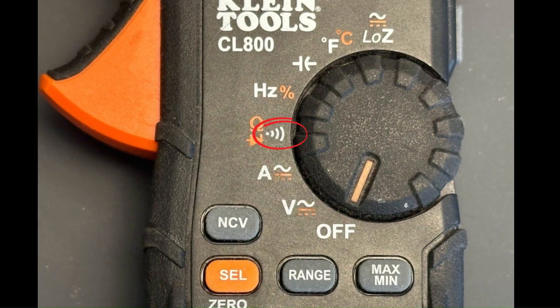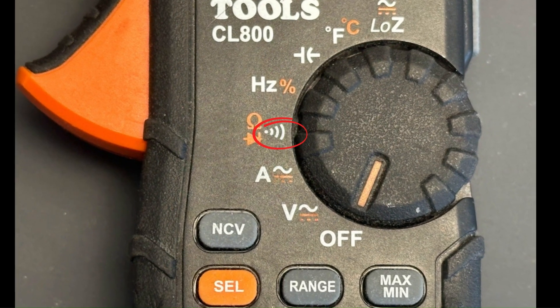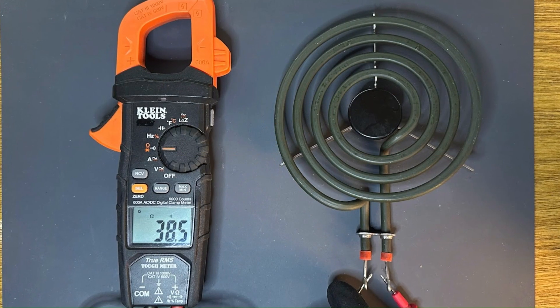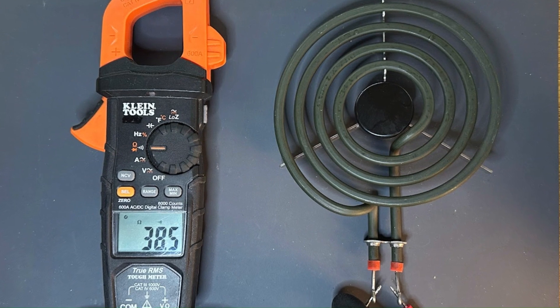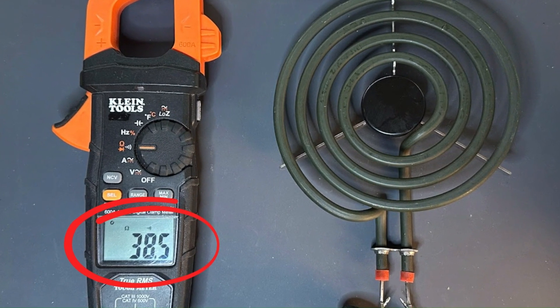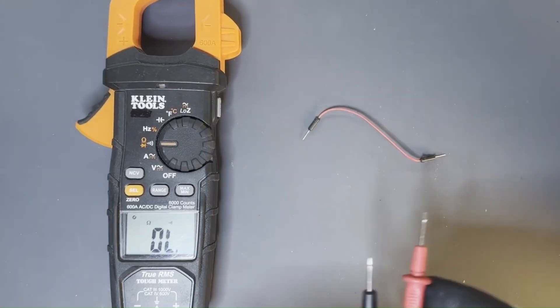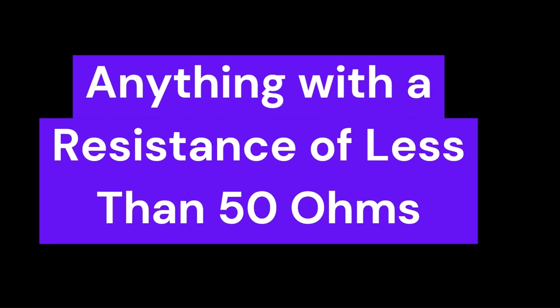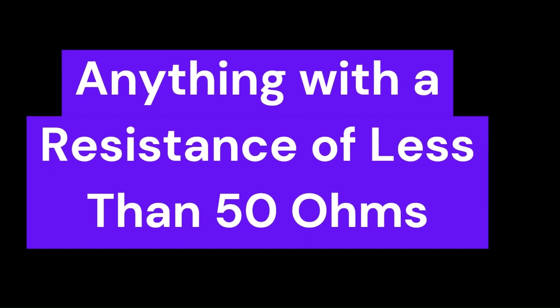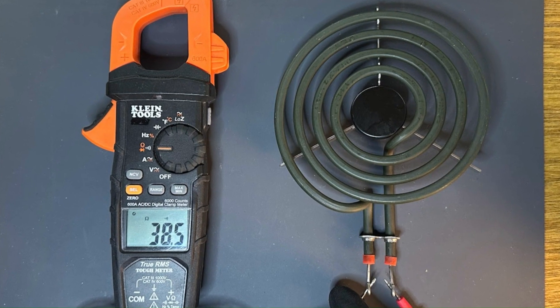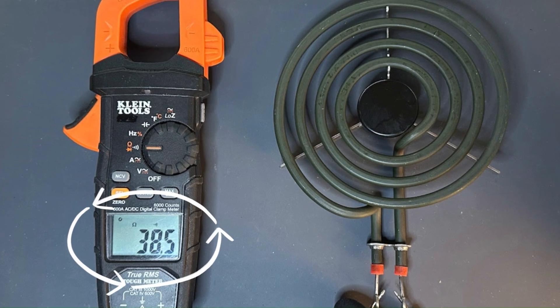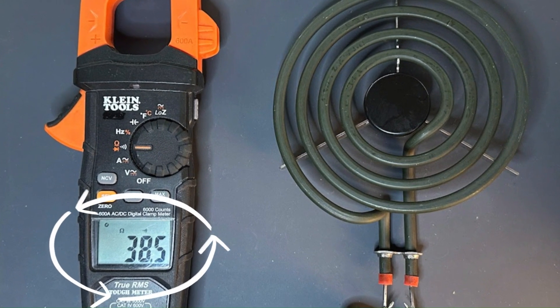Continuity check. Lots of meters have something called continuity check. It is a quick and convenient way of indicating whether a very low resistance is present — less than 50 ohms for this meter. This is handy for testing wires, low ohm loads like heating elements, and anything that has a resistance of under 50 ohms. In this mode, the meter will beep when it detects continuity and if under 50 ohms will also show its actual resistance. To access this mode, simply turn the dial to the same place you use to check for resistance.